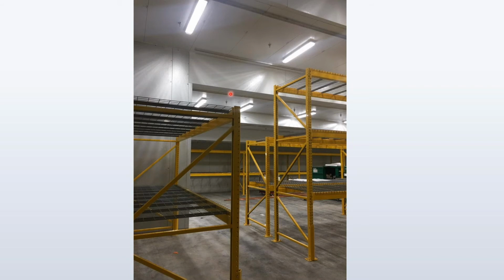There are some other things that come into play on a large walk-in as well. Once the walk-in gets over a certain width, the roofs have to be supported. In this case, the roofs are being supported by using what's called roof support channel. Steel channel is affixed to the inside of our roof panels and then suspended from the building roof above the walk-in. Another option would have been to work with a pallet rack manufacturer. We could have taken these pallet racks all the way up to the ceiling above them and then sized and located our panels so that they would just sit directly on top of those pallet racks for support.